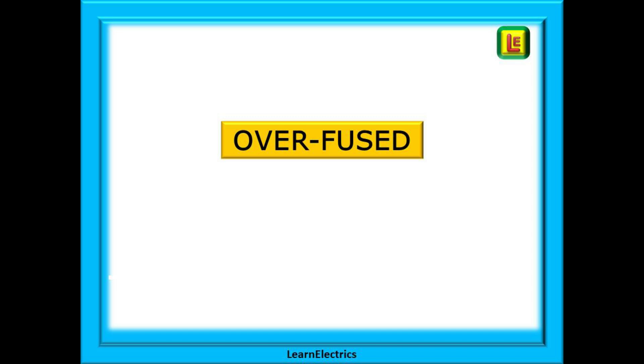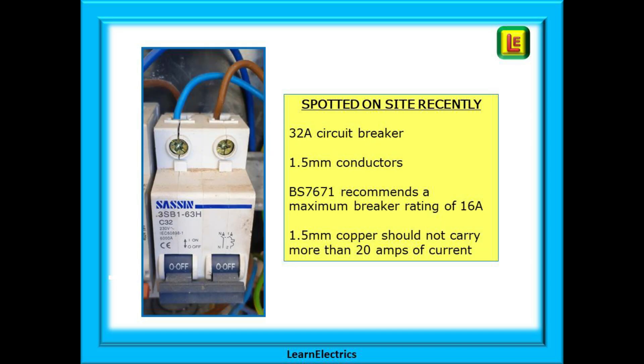Let's begin with an example of over-fusing. This happens when a circuit breaker or a fuse is installed that far exceeds the expected working current of the circuit, and this is often the result of the person installing it — the householder doing some DIY — not knowing what they are doing. This example shows a 32 amp breaker protecting a lighting circuit that is wired in 1.5 millimetre conductors, spotted on site recently. BS 7671 recommends that circuit breakers for lighting circuits should be 16 amps as a maximum, and in this case 6 amps would have been more than sufficient. Also, 1.5 millimetre copper conductor has a maximum rating of 20 amps. This shows the importance of visual checks.